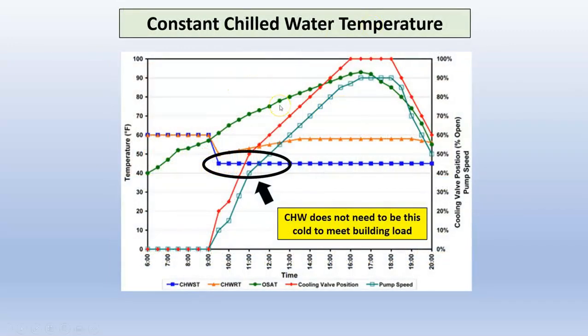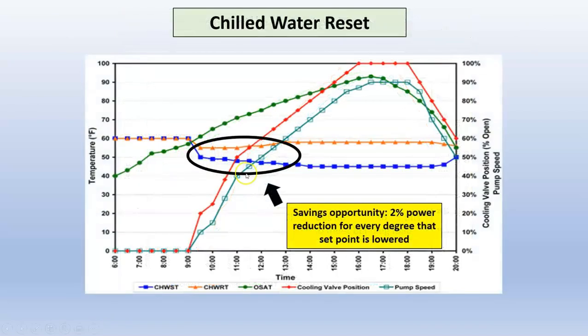Chill water temperature set at 42 degrees, set it and forget it. Not necessary. You don't need to be this cold to meet the building load during cooler temperatures. As you can see here, when I let it reset, I can crank that temperature all the way up to like 50 degrees or so. And the old saying, or the thumb rule, 2% power reduction for every degree. When you're talking a 300-ton chiller, that is a whole lot of money that you're going to save just by resetting the chill water temperature.